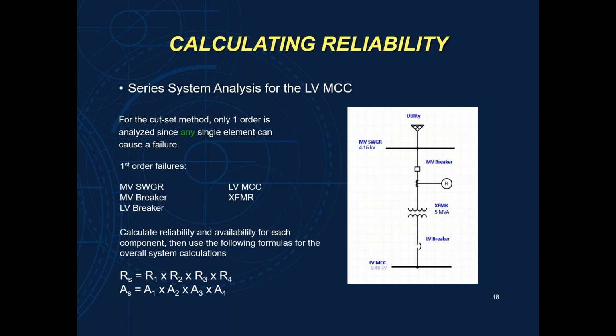So our first order failures here, we have our switchgear, we have our low voltage and medium voltage breakers, we have our low voltage MCC, and we have our transformer. If any of those fail, then we're not going to be able to produce out of this MCC. On the bottom left, your reliability, again a percentage, and your availability being a percentage, the calculations are pretty straightforward. For each component, R1, component R2, component R3, these are your individual components. And as you can see, the calculation is you multiplying their reliability percentages and their availability percentages together.